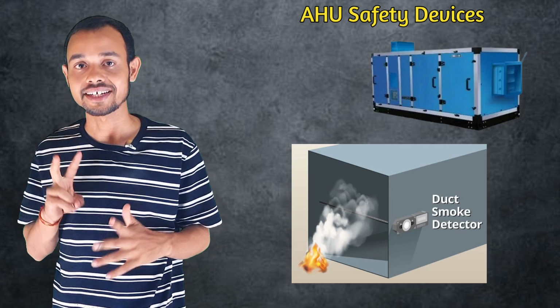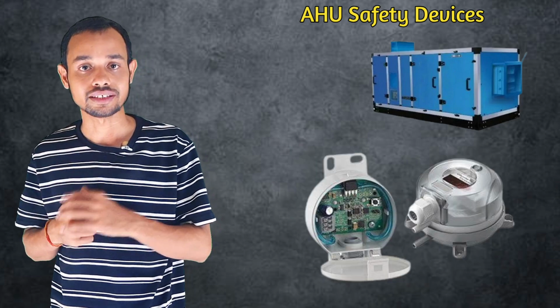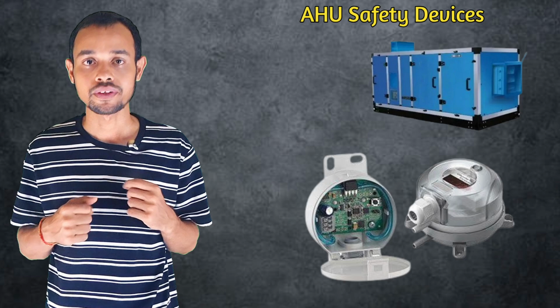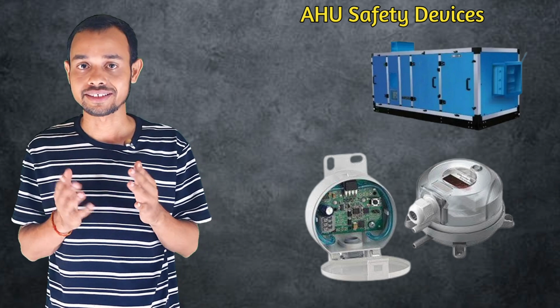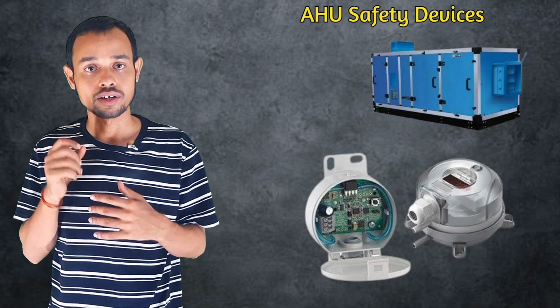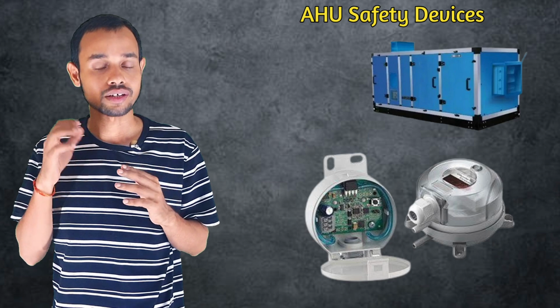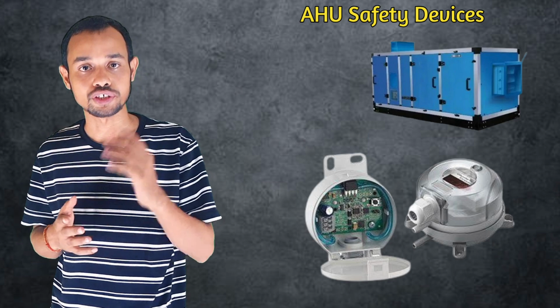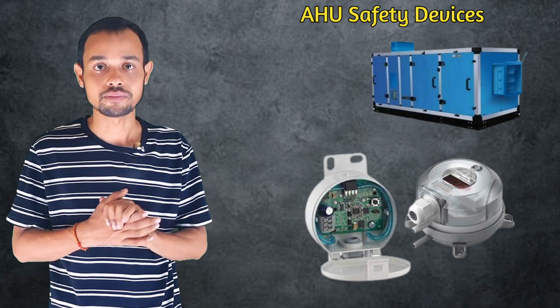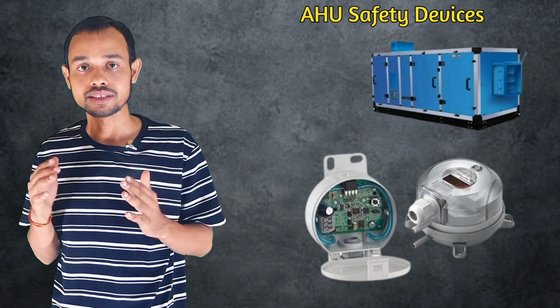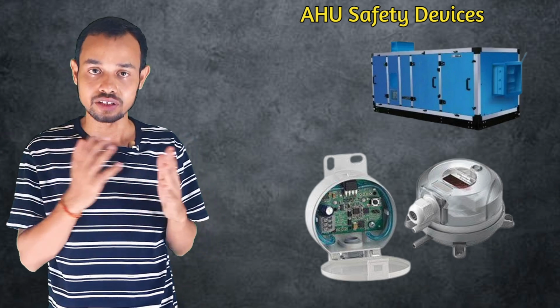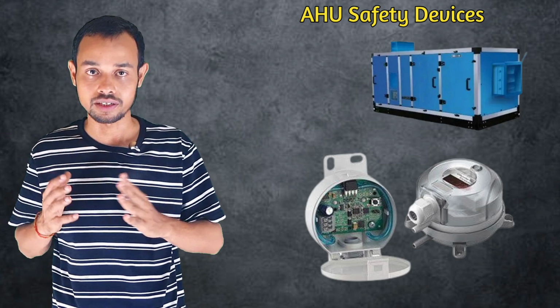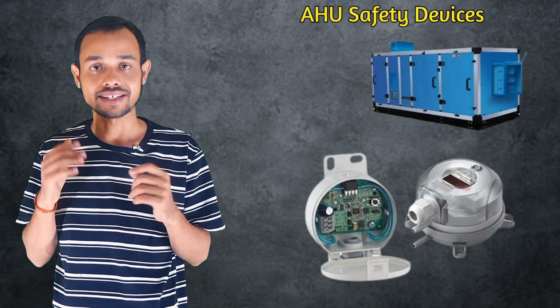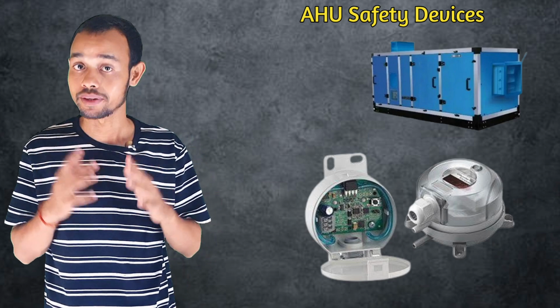And second is the differential pressure switch, the DPS switch. If the filter is choked or the fan does not run properly, the airflow reduces. The differential pressure switch immediately detects when the pressure differential between the inlet and the outlet becomes abnormal, preventing the system from getting damaged due to the airflow being blocked.